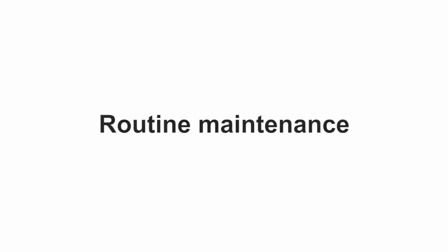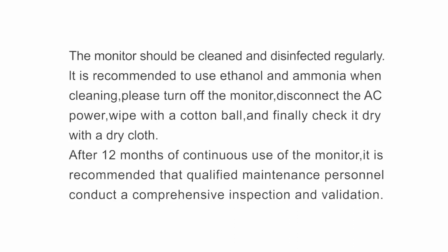Daily maintenance. The monitor should be cleaned and disinfected regularly. It is recommended to use ethanol and ammonia. When cleaning, please turn off the monitor, disconnect the AC power, wipe with a cotton ball, and finally dry with a dry cloth. After 12 months of continuous use of the monitor, it's recommended that qualified maintenance personnel conduct a comprehensive inspection and calibration.